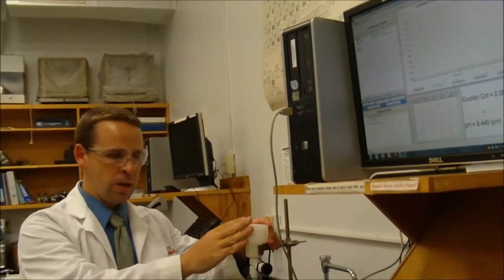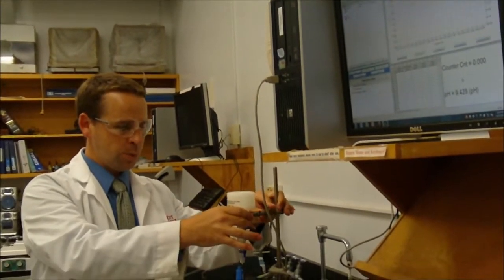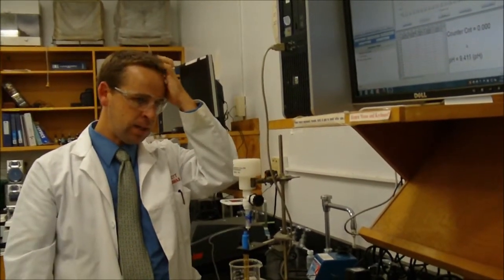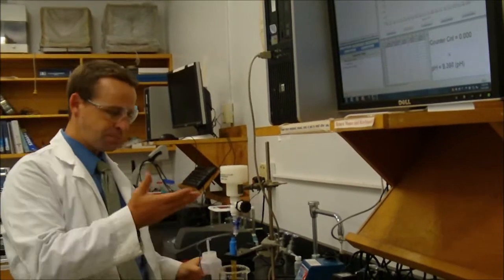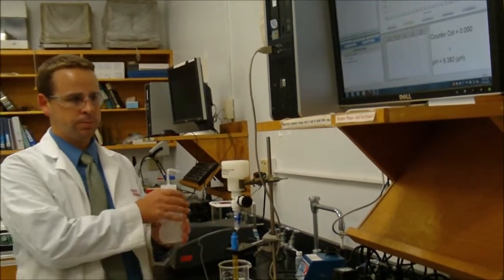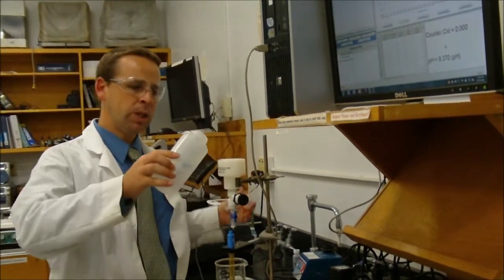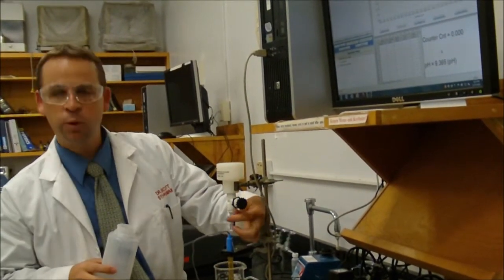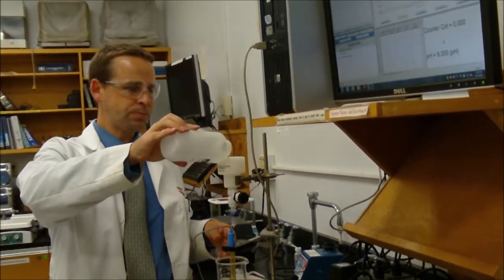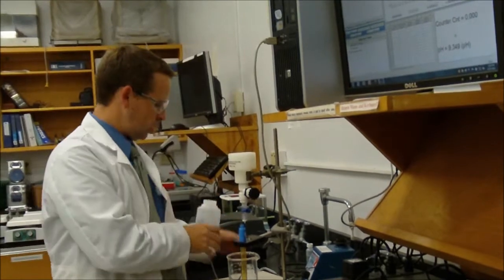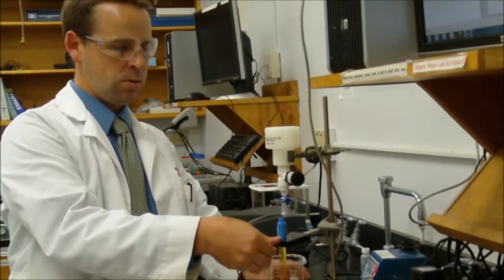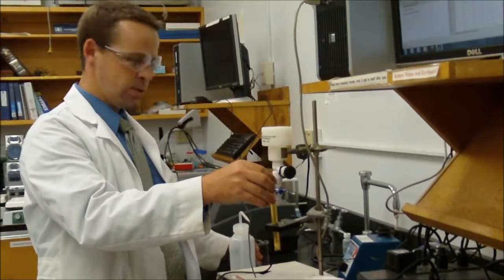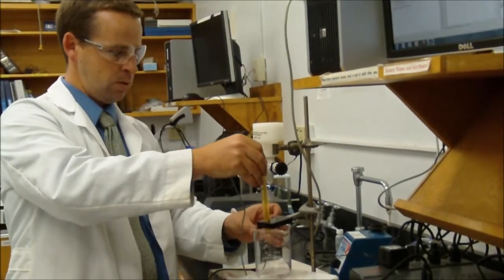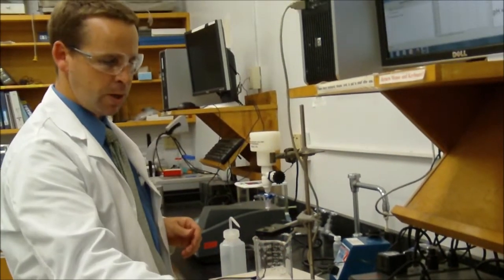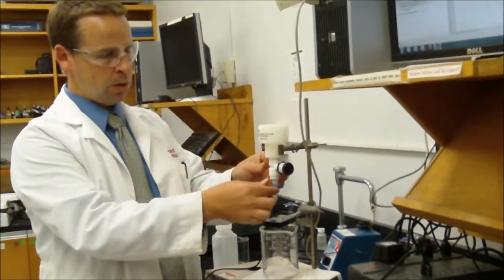Now I want to line up my counter here to make sure that it's going to drop at the appropriate spot. Okay, to do that I need to put a liquid in here, and here I'll just put water in. I also want to make sure this is closed before I put the liquid in so it doesn't just come pouring out. And this might be my titration vial here, or vessel. So maybe I'll take my waste vessel and put it underneath here. Okay, and I don't need my pH probe in there for now. So now I can use this water to try to line up my drops.